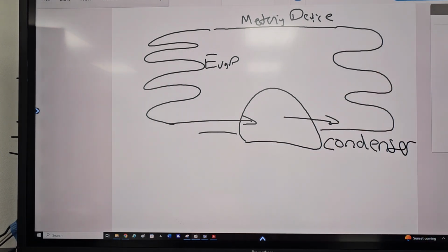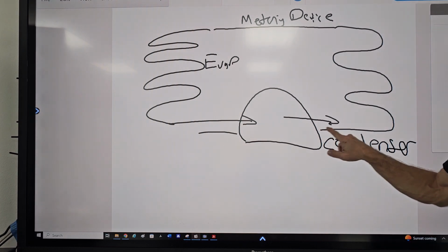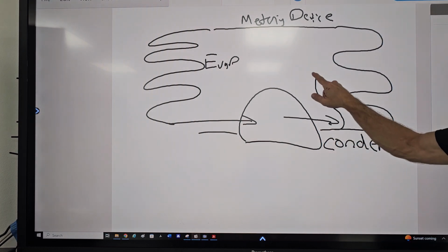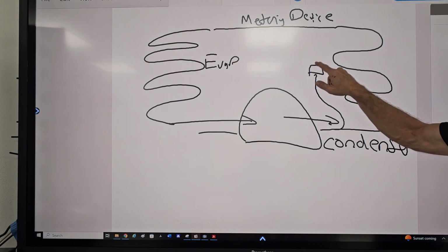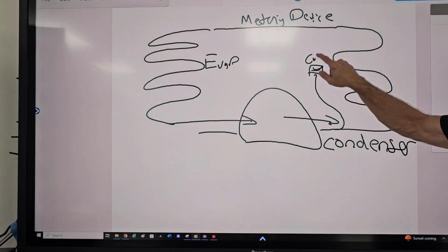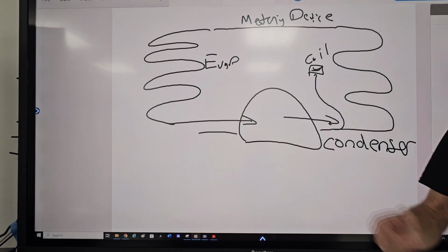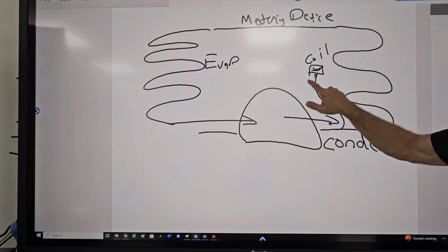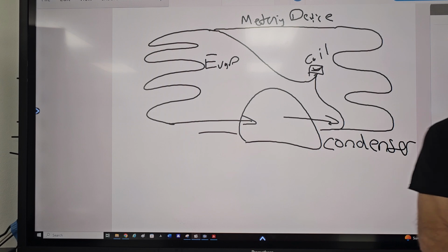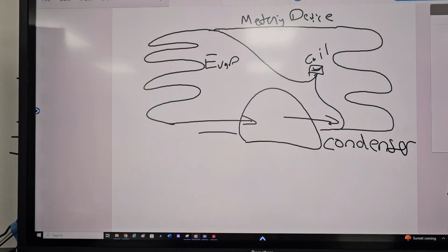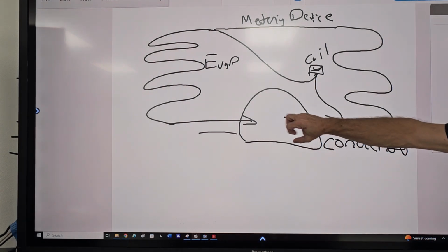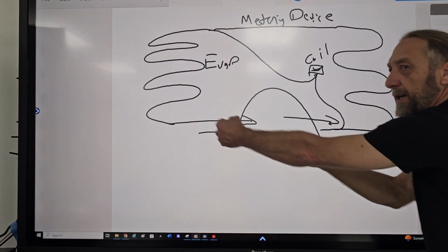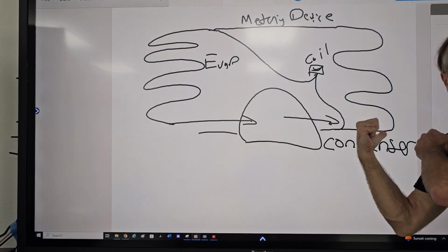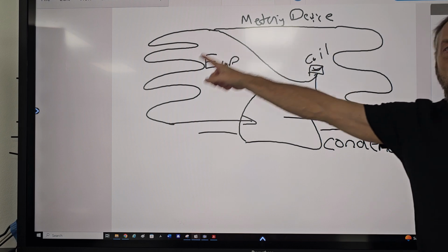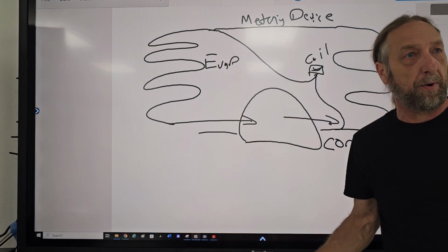Now, we added something called a hot gas valve. So right here on the compressor is a second pipe to a magnetic coil called a hot gas valve, and that coil connects to here. Now what happens in a regular refrigerant system, it's pumping into the condenser, it's pulling the Freon from the evaporator and pumping it over here. But if the pipe's all the same size, as soon as I pump, it just goes right around.